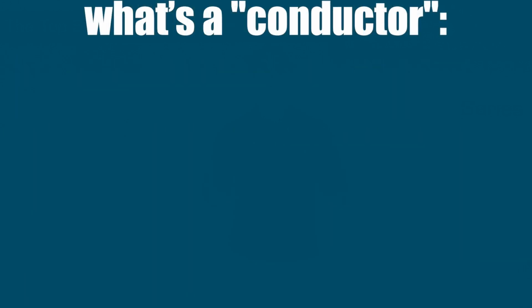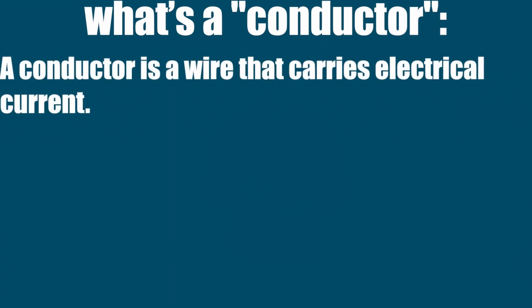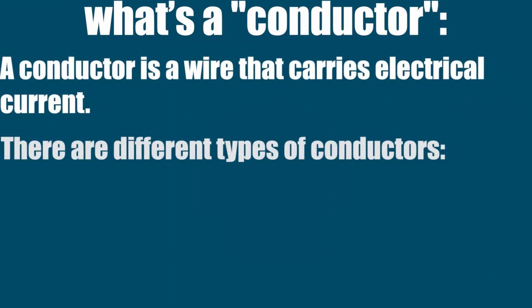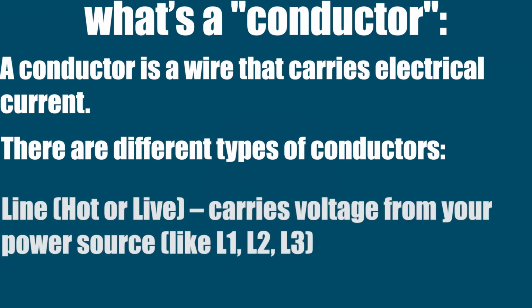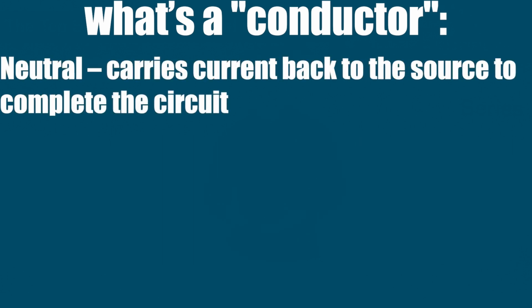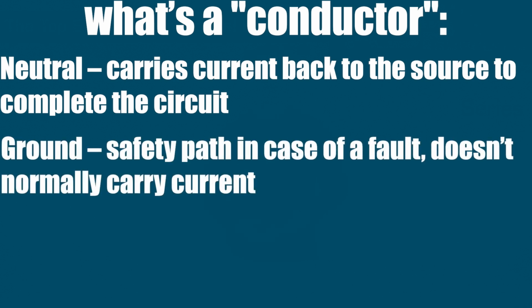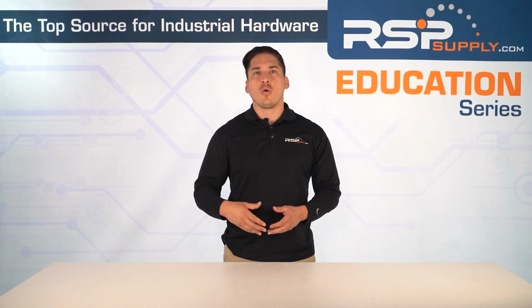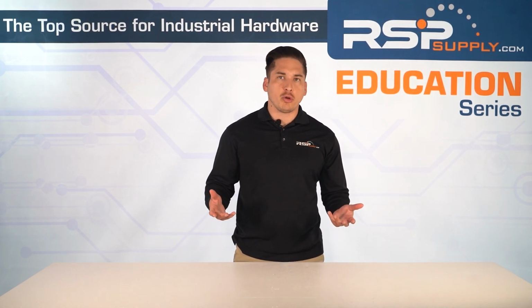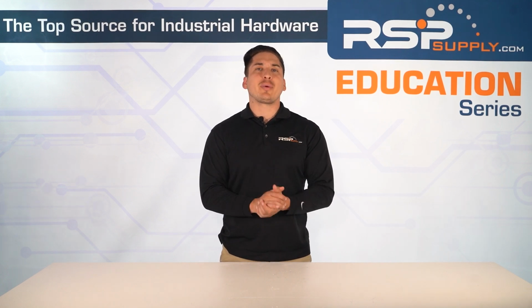So what's a conductor then? In simple terms, a conductor is a wire that carries electrical current. There are different types of conductors. You have line or hot or live. So line or live, this carries voltage from your power source like L1 or L2 or L3. Neutral carries current back to the source to complete the circuit. And then you have your ground. That's going to provide a safety path in case of a fault. Doesn't normally carry current. Poles are designed for switching the line or the live conductors and sometimes the neutral too, depending on your system.